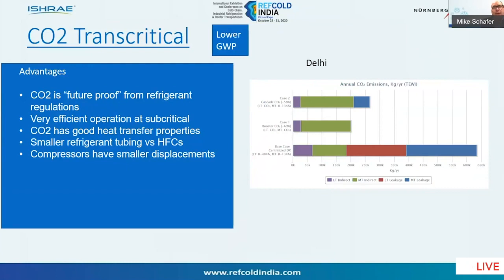CO2 has very good heat transfer properties in terms of volumetric efficiency, as well as latent heat of vaporization, and that results in smaller tubing sizes. So therefore, the installation costs will also be directly related to that in terms of the refrigerant piping. And the compressors have smaller displacement, but not necessarily smaller motors because of the high compression ratios.